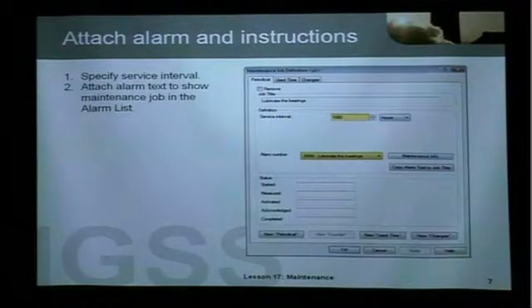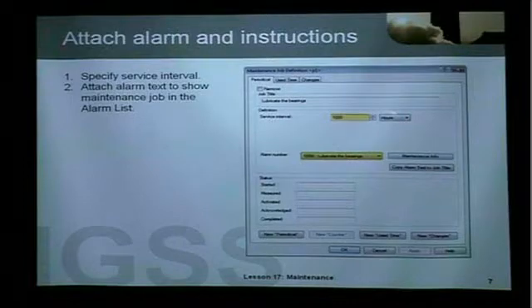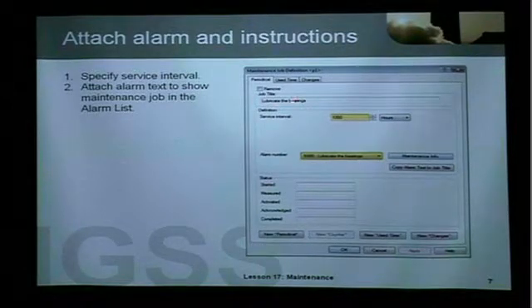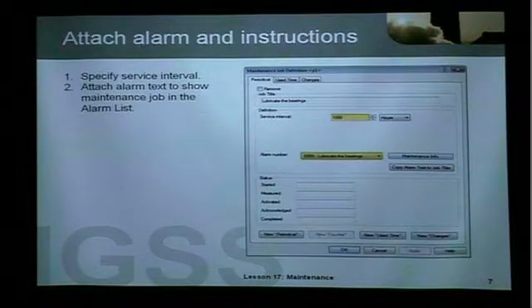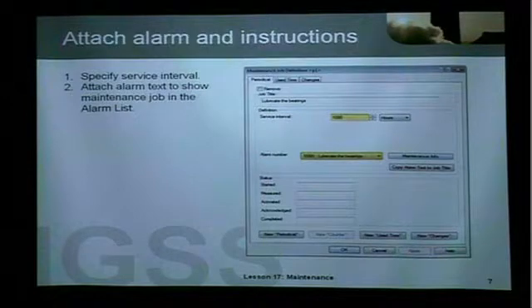I click OK and I get a tab for each maintenance type I selected. Under periodical, I have created a maintenance job. I have a title — Lubricate the bearings — that's what I want the service personnel to do. I want them to do it after 1000 hours from when I set this in motion. I can also show this maintenance job in the alarm list, but that requires attaching an alarm text from the definition module. I have attached alarm number 5000, Lubricate the bearings, and I can copy the alarm text to the job title for correspondence between the maintenance list and the alarm list.